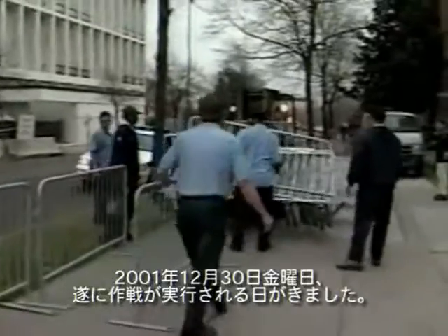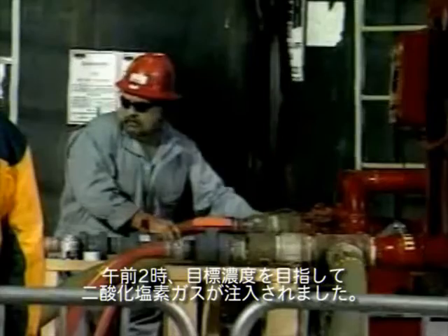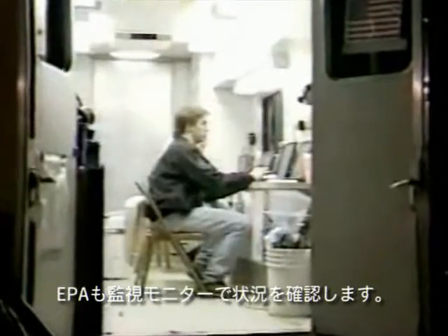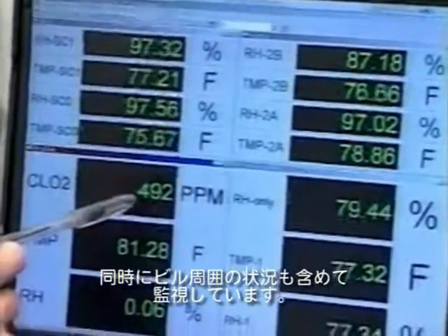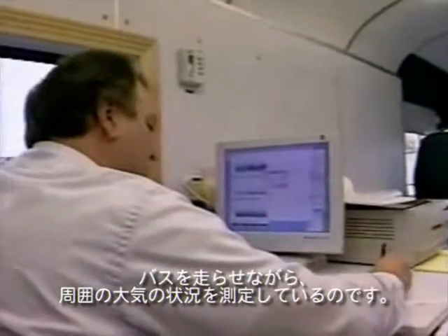Finally, on Friday, November 30th, Capitol Hill police secured the surrounding streets, and employees in the adjoining Dirksen building were sent home early so the system could be put through its paces. By 2 a.m., humidity had reached target levels, and ClO2 was pumped into the building. The EPA's Environmental Response Team performed perimeter air monitoring as a precautionary measure to ensure the surrounding public was not at risk of exposure to any fugitive emissions of ClO2. ERT's TAGA, or Trace Atmosphere Gas Analyzer Bus, also circled the site, collecting real-time air samples.